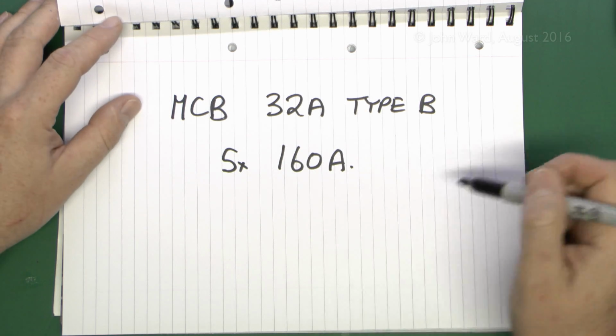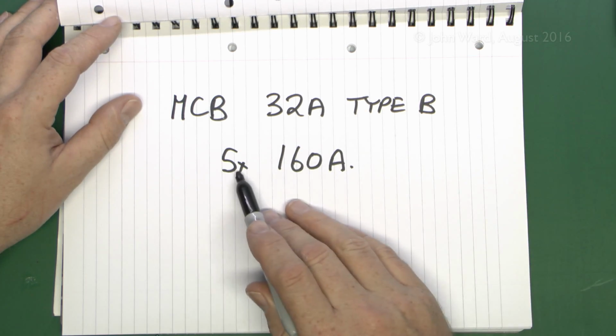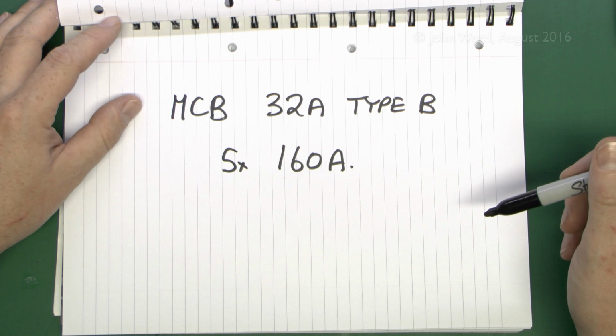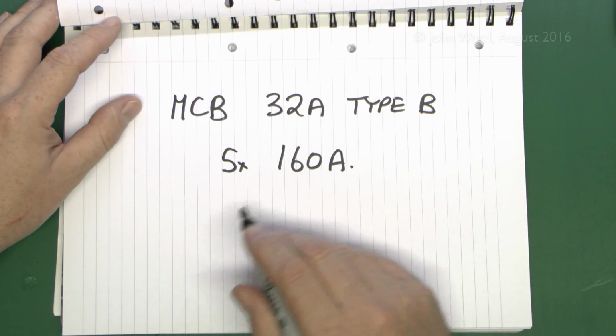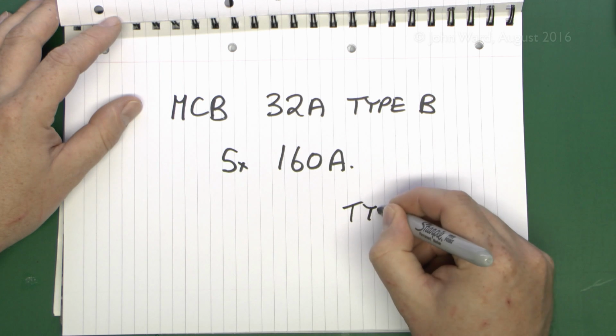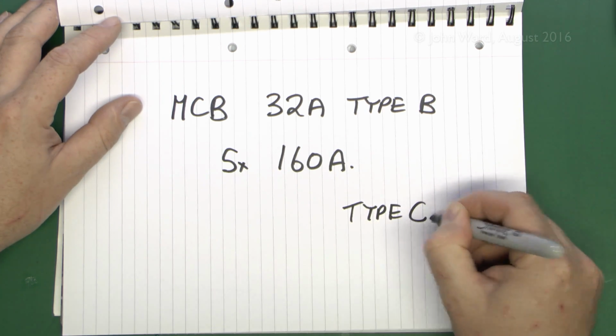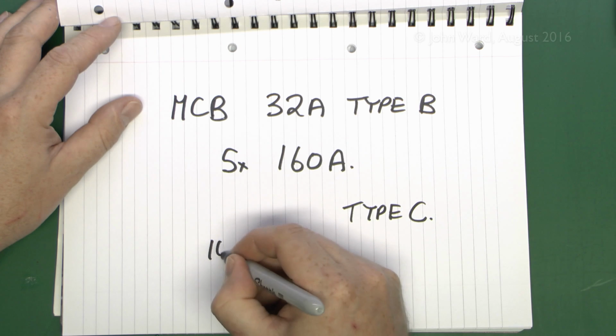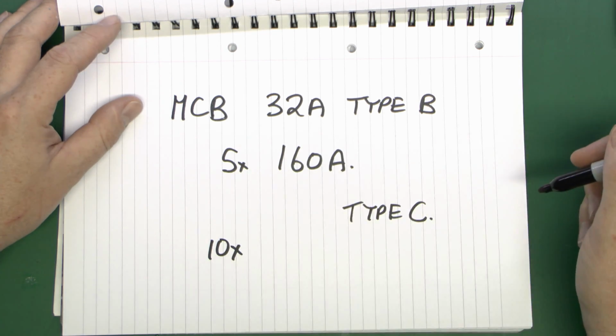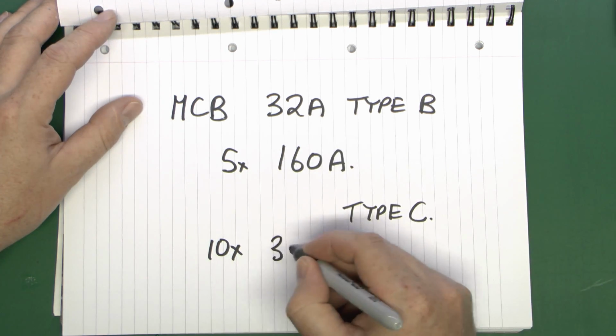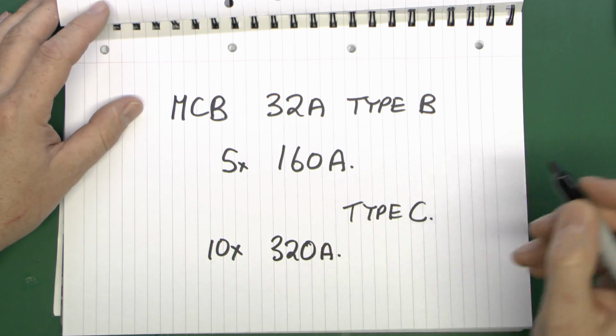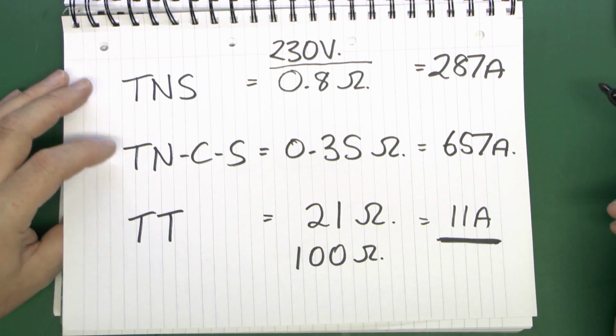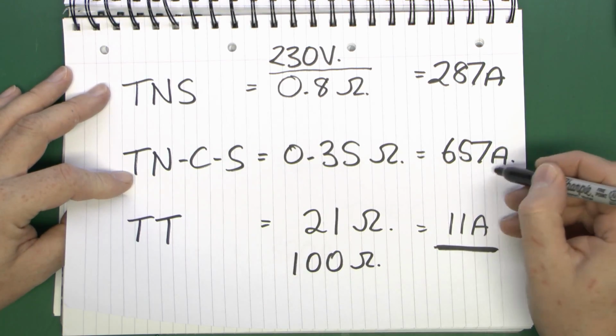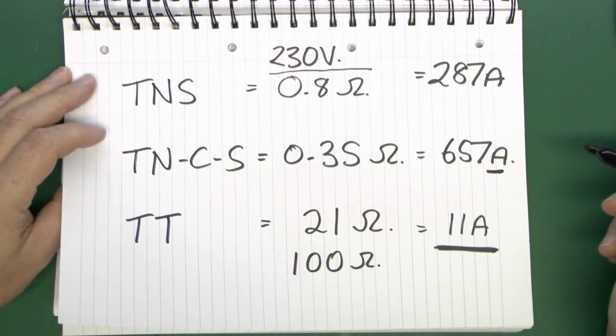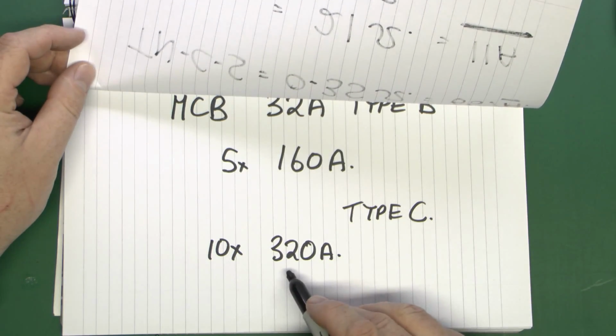So that's with a type B there, and again that typically runs around 5 times the current rating to trip. However, in the case of other types, there are, for example, a type C. Type C requires 10 times the current rating to trip, so in this case it would be 320 amps. Now, have a look on the fuse page. Well, with the TNCS supply, again, short circuit current is going to be around the 657 amps range, so again, massively more than 320, not a problem.